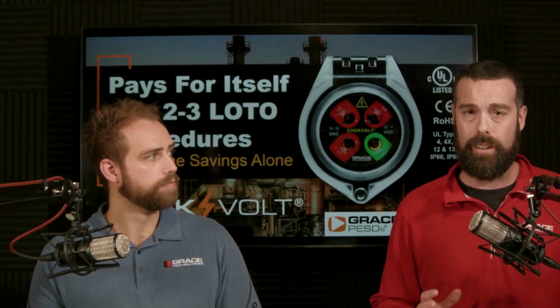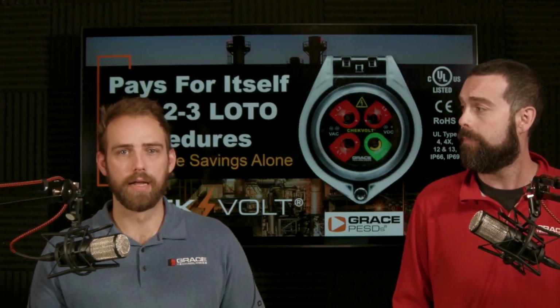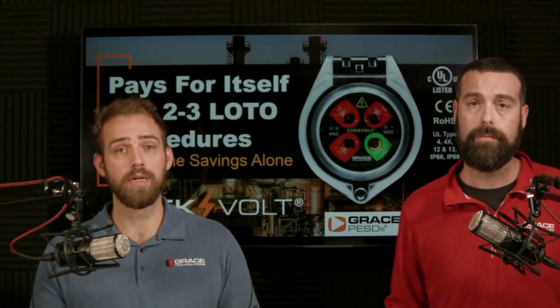And as Ben's kind of alluding to, it's all contained within the device itself. You push the button, it'll do that continuity test and spit out a green, red, or yellow LED to confirm whether or not the voltage is absent. Yeah, the lights basically indicate if it's dead or if you still have live voltage or hazardous voltage present. So the main difference I would say is that the AVT is a push button. So the preference depends on whether you want to use a push button for electrical lockout tagout, whereas the ChekVolt is for your multimeter. So you're still allowed to use your standard multimeter to confirm dead and for electrical lockout tagout.